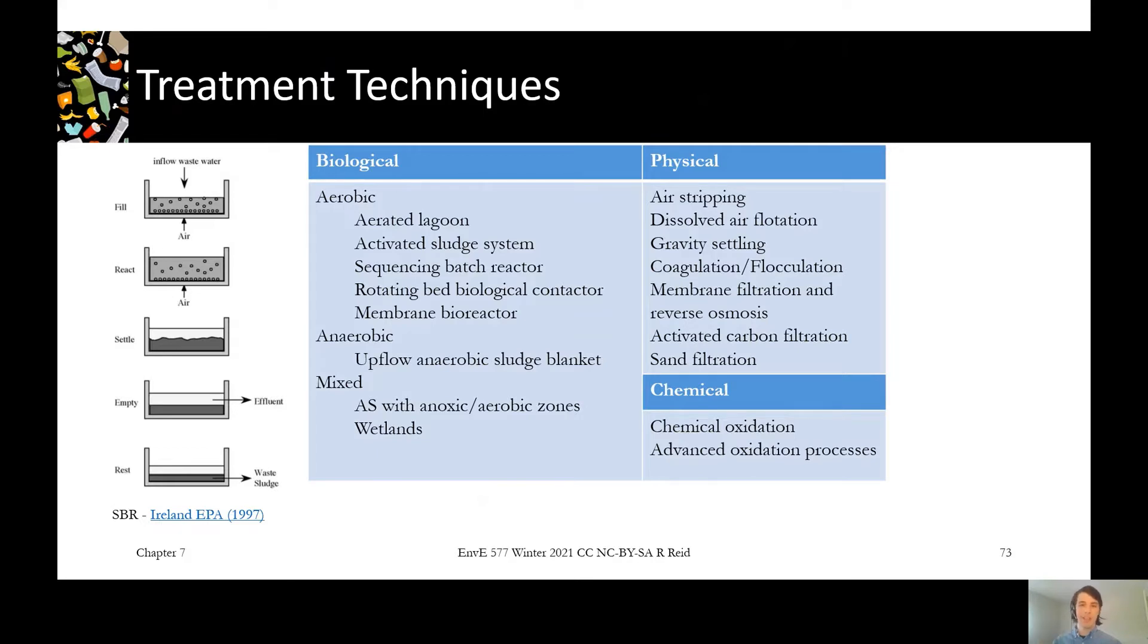Coagulation flocculation can encourage some of those suspended solids to come out. Membrane filtration and reverse osmosis is going to go from small solids all the way down to the molecular level and reverse osmosis will get us very high effluent quality. It'll remove those chlorides. It just takes a lot of energy to do it. So you might do some other solids removal steps before you get there.